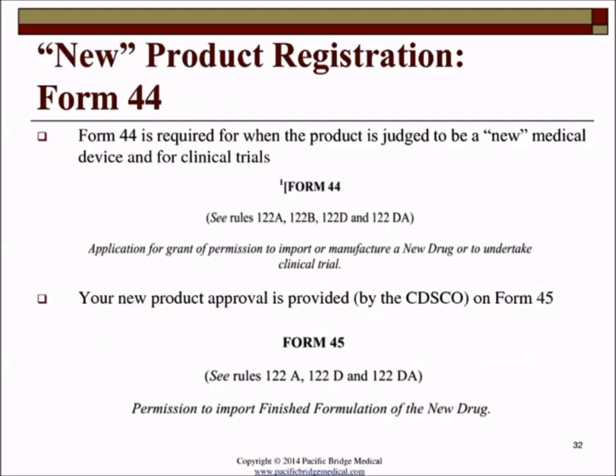Now, if you have a totally new product, you're going to use Form 44. And Form 44 is required when the product is judged to be a new medical device and requires clinical trials in India. And keep in mind that this is because some of the medical devices are still classified as drugs and are therefore subject to some of the same regulations as drugs for new medical device registration.